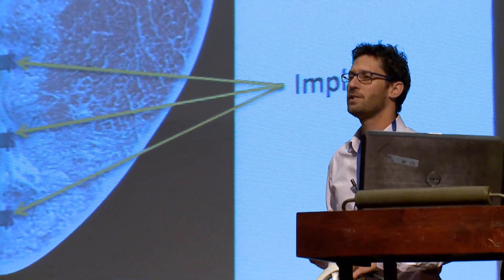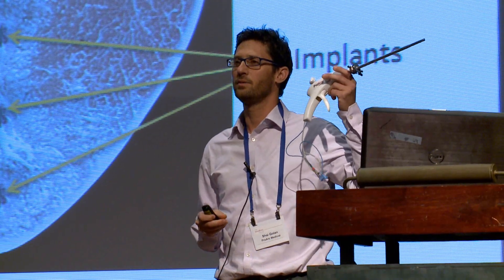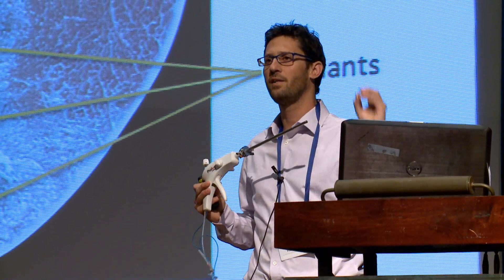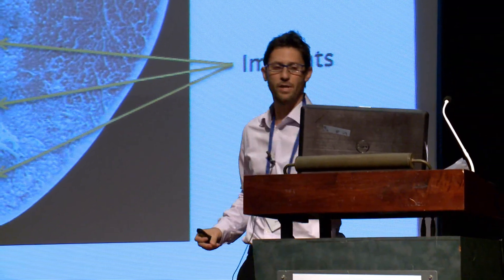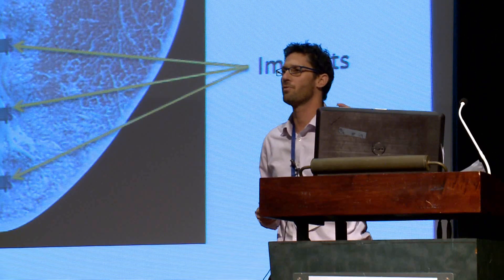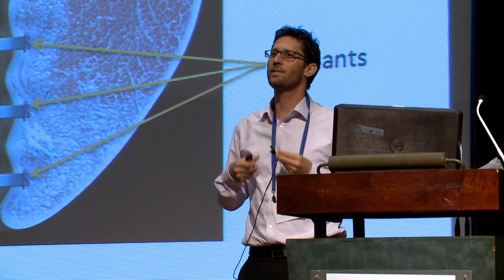We saw enough — this is the reason we developed our device. Our device includes a unique implant with a dedicated delivery system. The implant, in the shape of an open ring, is placed within the prostate tissue surrounding the urethra, as you can see in the illustration. Such implants expand the obstructed area and allow you to urinate freely.